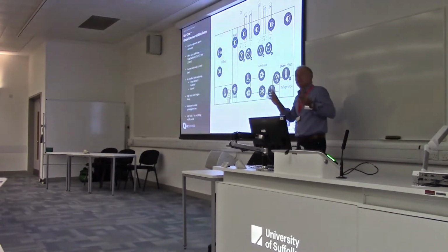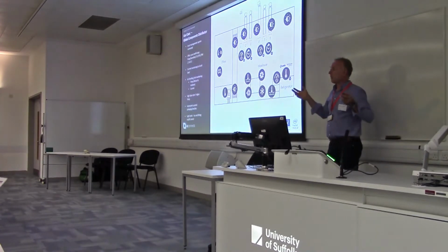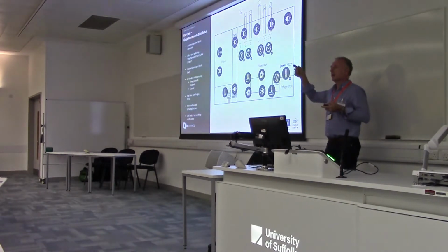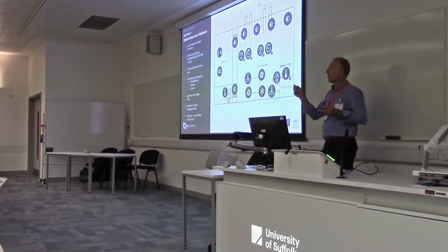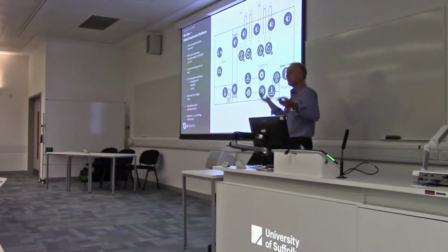And again, lighting control. You didn't need a full-fledged lighting control system. We just effectively intercepted some of the circuits for some of the lights, put in a lux sensor, and then we used the software to make sure that whatever the lux levels were at certain points, we were just using simple £35 relays to drop lights off to save energy as it went along. All works beautifully.